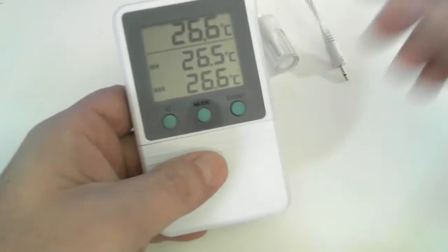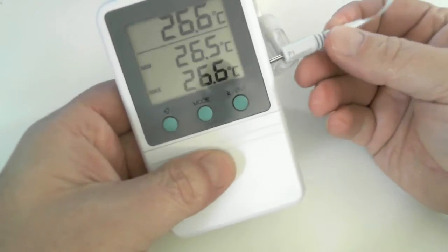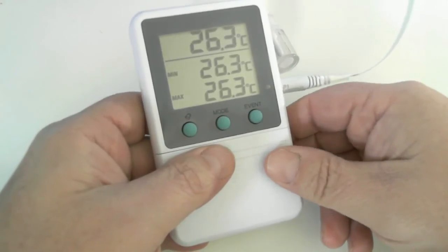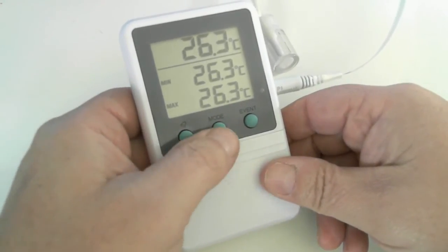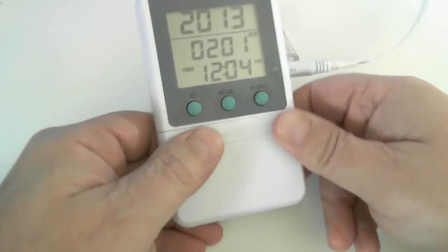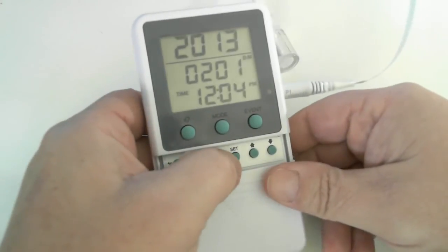All right, so let's plug in our external bottle probe. And the first setting I like to do is our time and date settings. So let's go to that screen. Open up our compartment. Hit the set button.